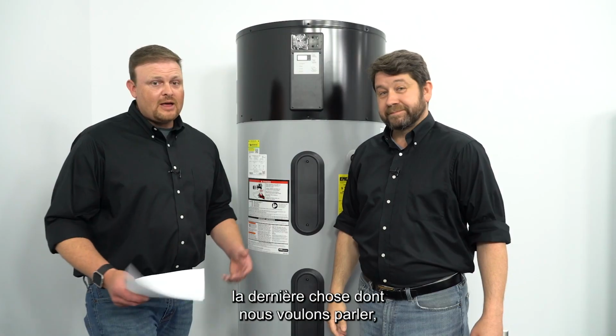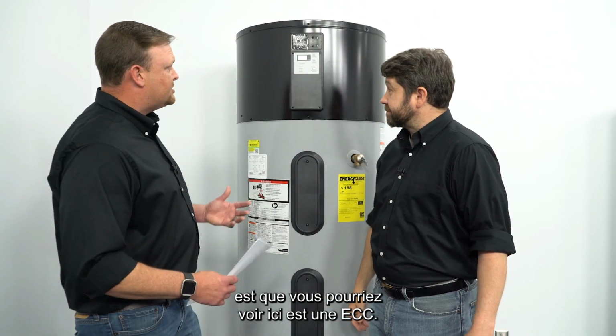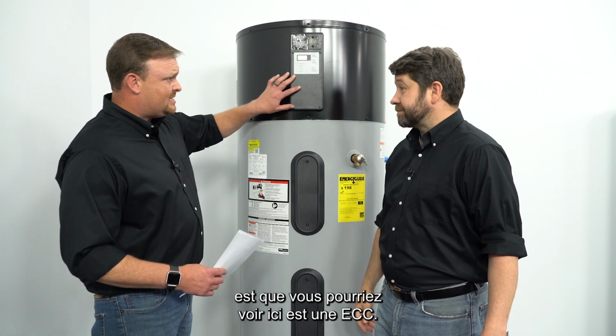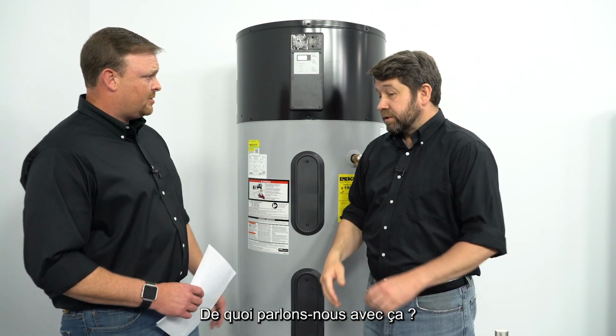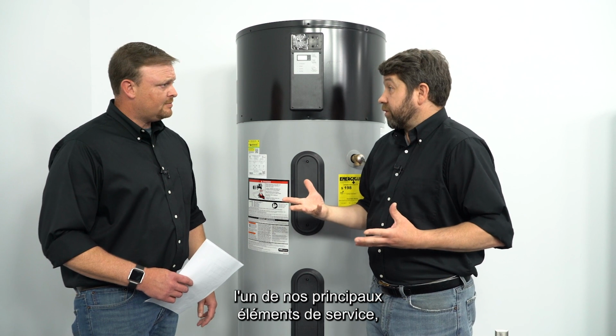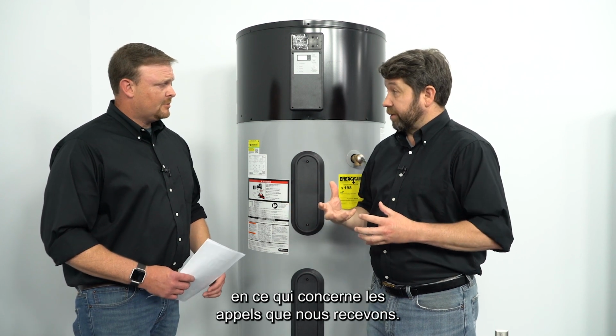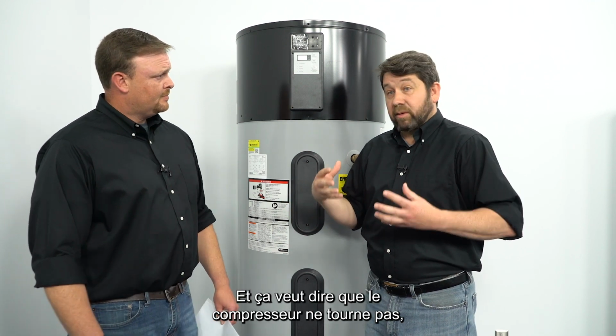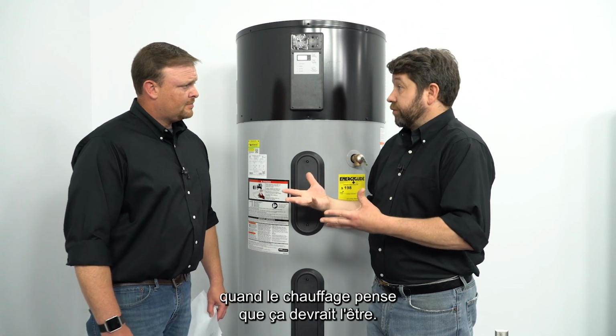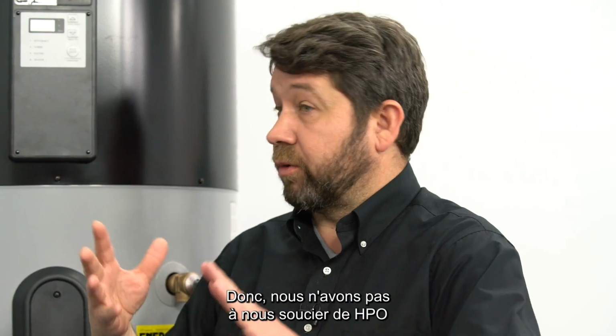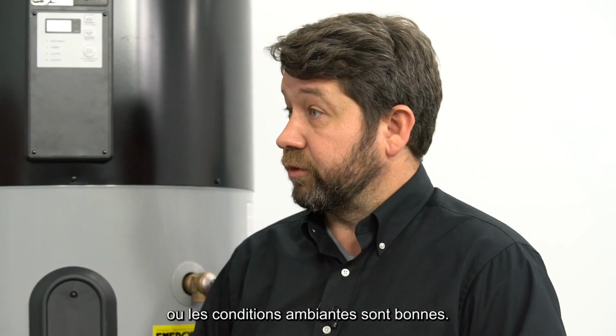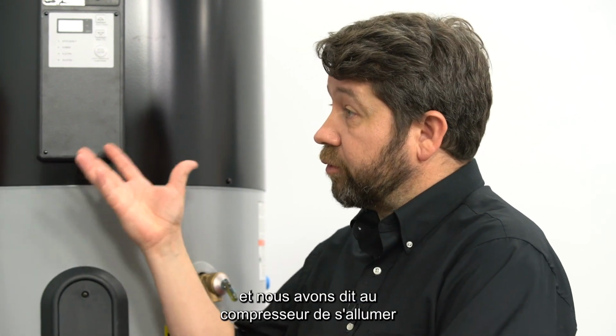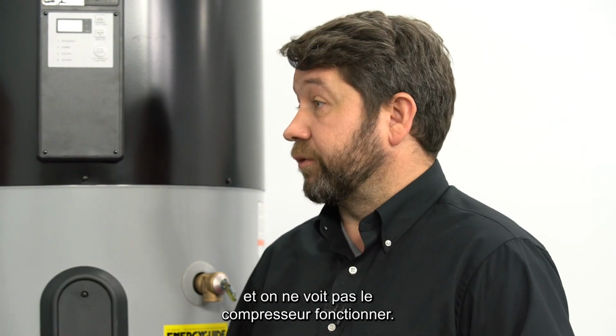All right. And now the last thing we want to talk about is, you might see on here, an ECC. What are we talking about with that? So ECC is probably one of our top service items as far as calls that we get. And what that means is that the compressor is not running when the heater thinks it should be. So we don't have to worry about HPO. Our ambient conditions are good. We've sent a call for heat. We've told the compressor to come on, and we don't see the compressor running.